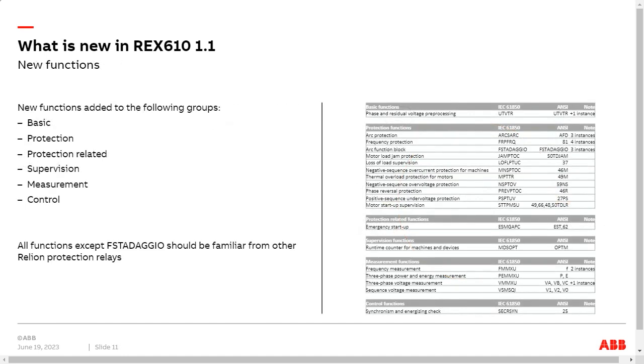Okay, what type of functionality has been added? I don't expect you to look at the groups, but it will give you a general idea. If you start from the table on the right from the top, basic functions, we now have an additional voltage pre-processing block. If you then go down in the table to the control functions, the last one, you can now see that we have the synchro-check function there. Due to this, we needed to add one pre-processing block for the voltages. And also if you go to the measurement functions tab, you can see that there is also +1 instance marked on the three-phase voltage measurements.